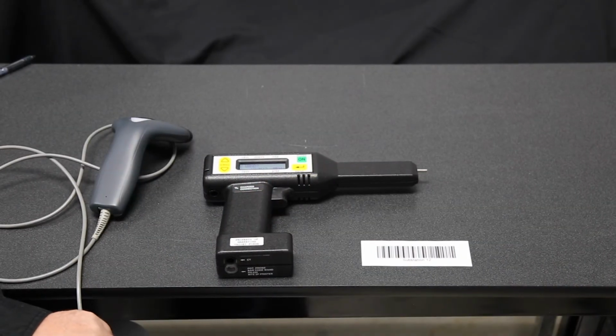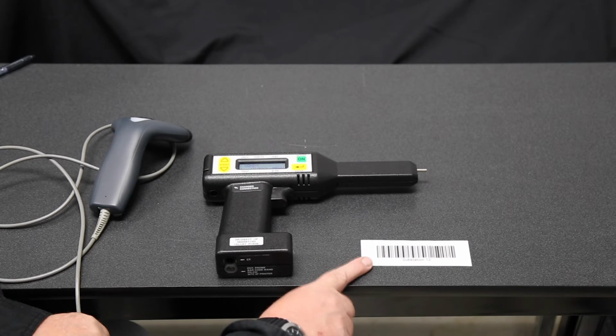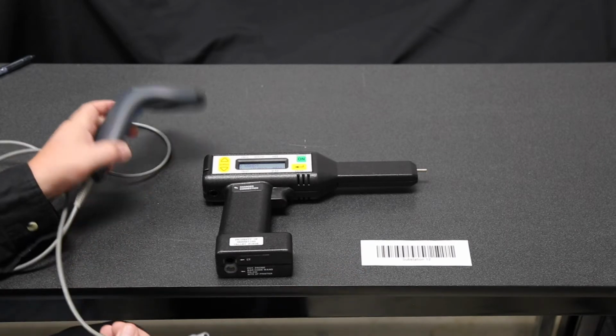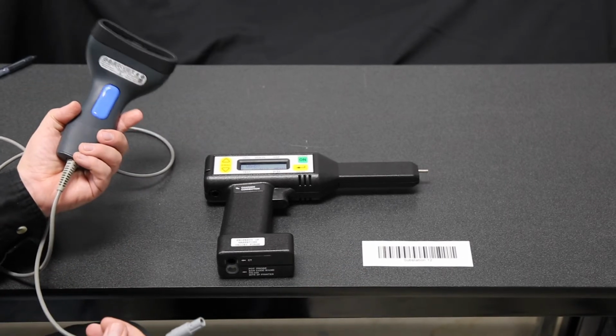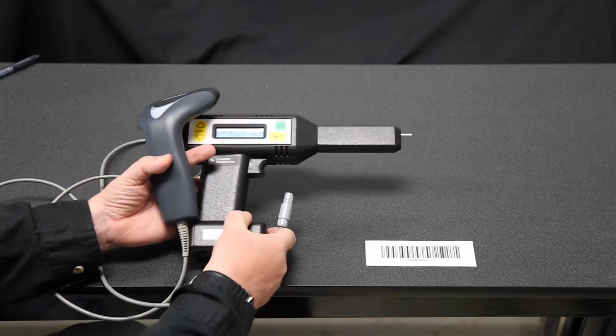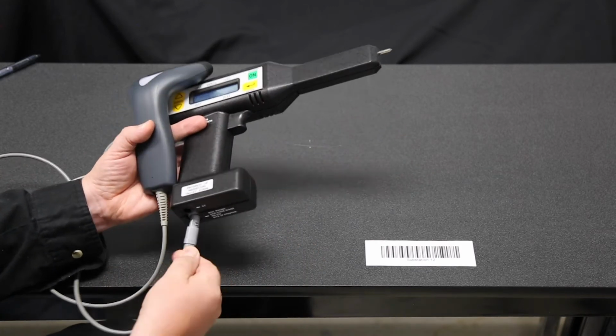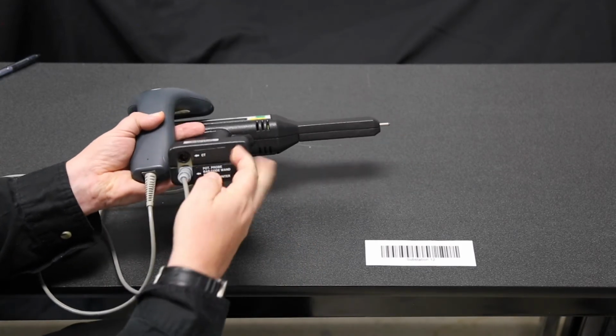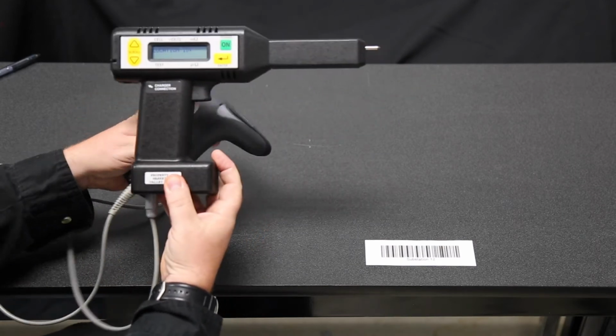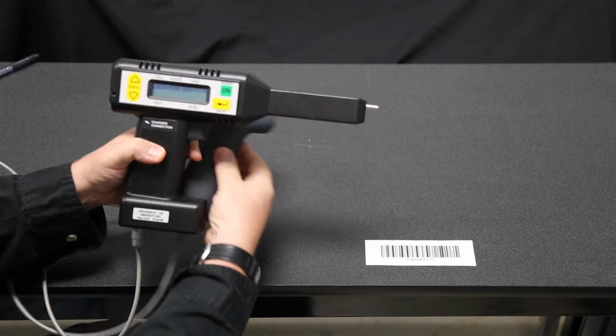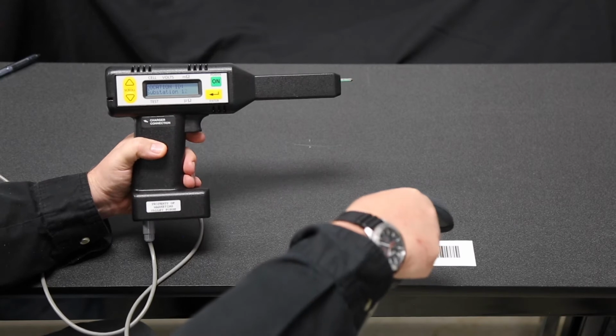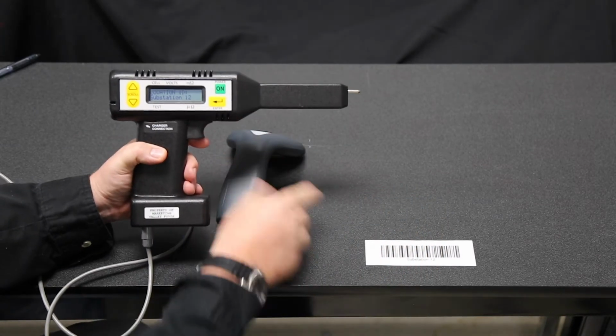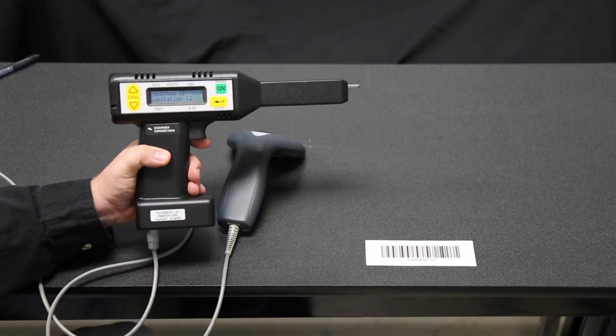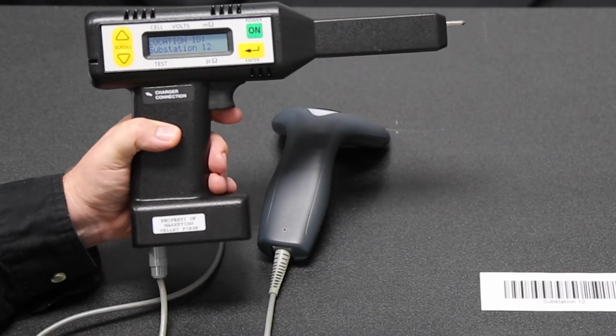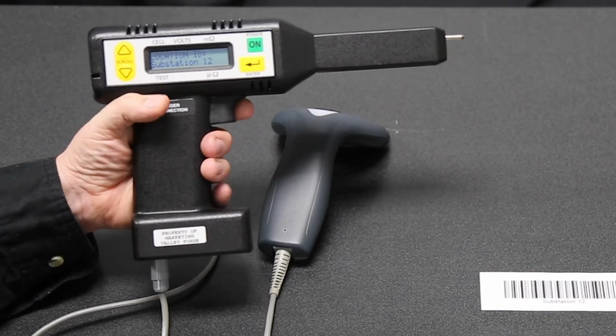If you are testing multiple strings each day, you may want to put a barcode on the string. You can then connect a barcode reader to the BITE2 and scan the battery string. And you can see it's now waiting for a location ID. And you can see now substation 12 is on here. So it now has the ID in there.